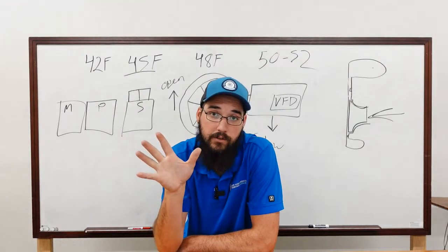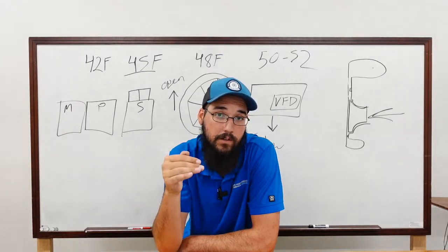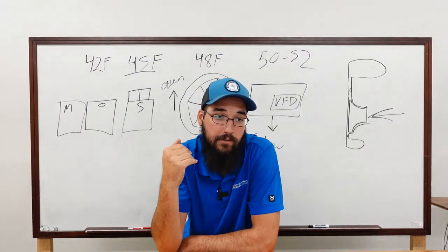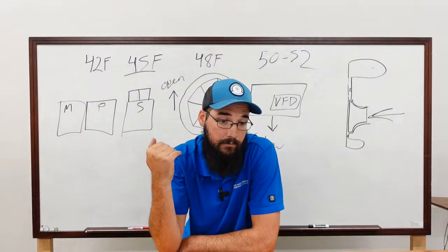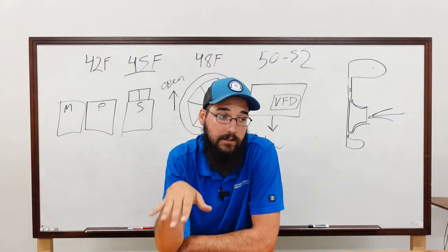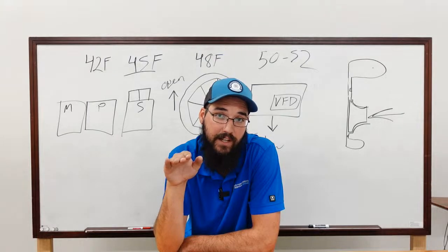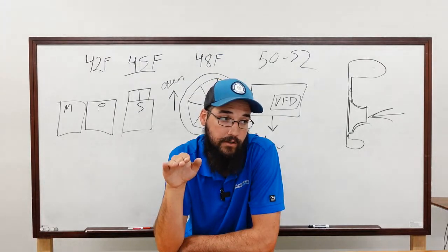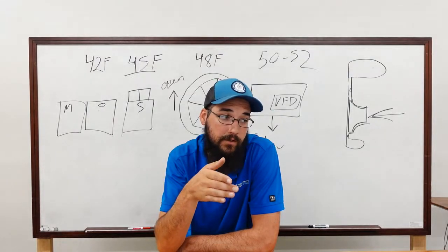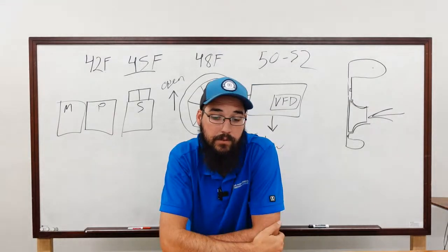So we have a really high condenser water, which at that point you should immediately, one, stop the chiller, stop the surging from happening. You can go straight to lowering the current limit if you want to try to catch it. But my personal opinion, if it's happening like that, I'm going to stop that machine. I'm going to then go in and make the adjustment to the current limit and then let the machine come back up so that it can come back at a more stable state and we're not already on the edge of surging then trying to back out of it. Because that means you probably still have a couple more surge opportunities in there before you reach the new current limit set point that you just put in place. That's my personal recommendation.